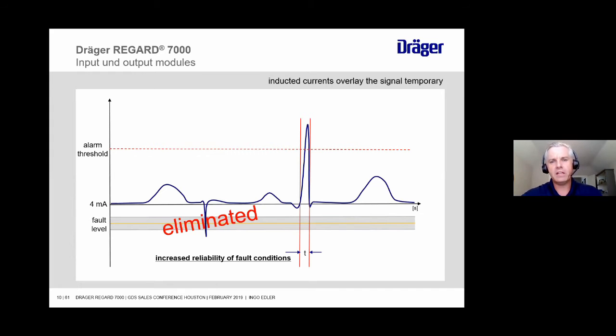So that next little big spiky thing is basically what I would consider is not gas. When gas comes in proximity with basically any of our sensors, it takes a little while for the transmitter to actually pick that up as actual gas. So those are the rounded curves that you see on that chart there. This big spiky thing, that's not gas. But on traditional controllers, they will call that gas.